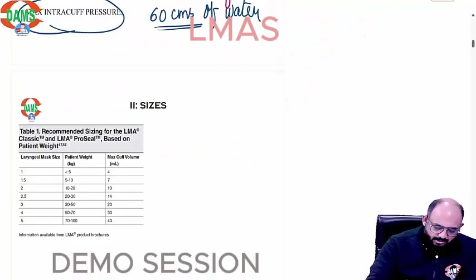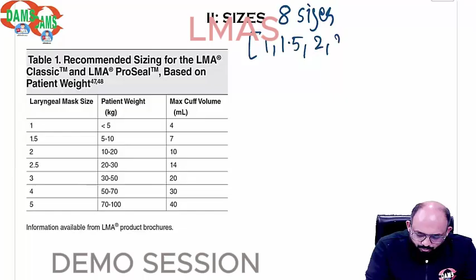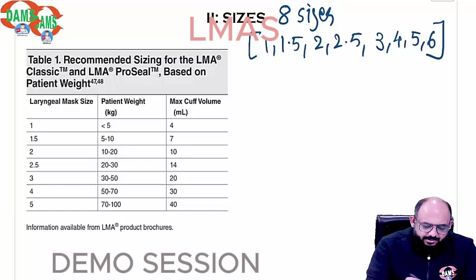Right? So this is a basic description of laryngeal mask airway classic, LMA classic. All right. Next, look at the sizes. There are a total of 8 sizes available, which are 1, 1.5, 2, 2.5, 3, 4, 5 and 6.